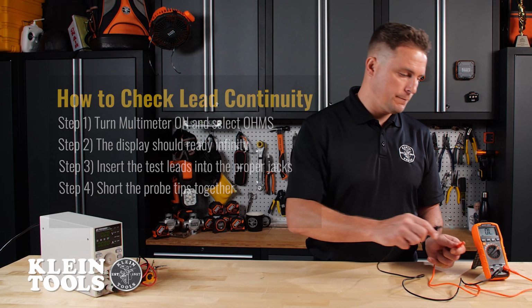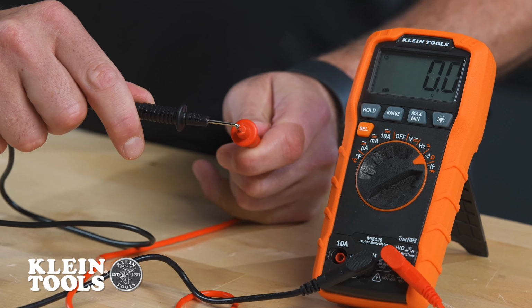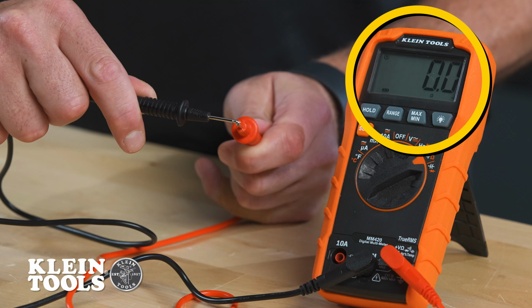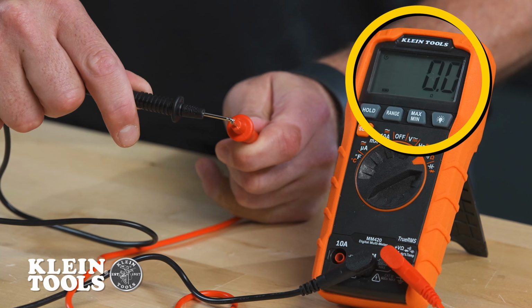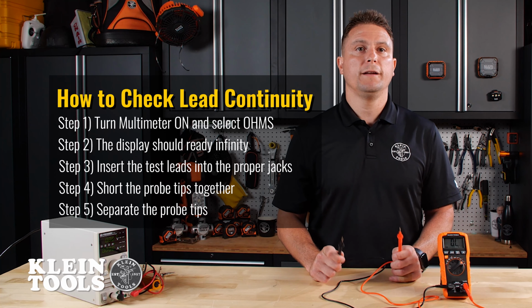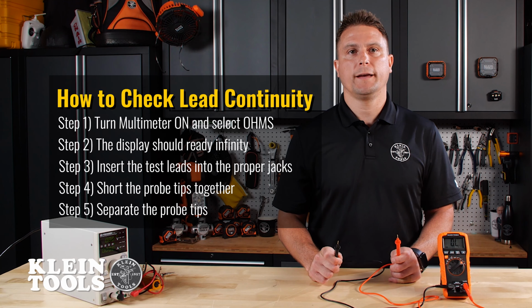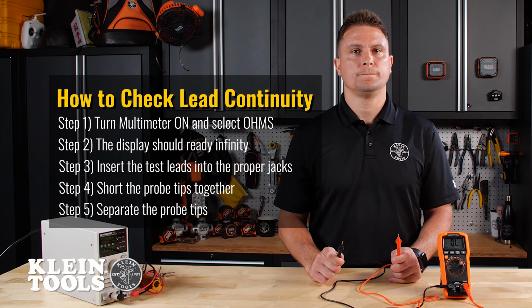Step number 4. Short the probe tips together. The display should read 0 and the continuity indicator tone should sound. Step number 5. Separate the probe tips. The display should again read infinity and the continuity indicator tone should be silent.